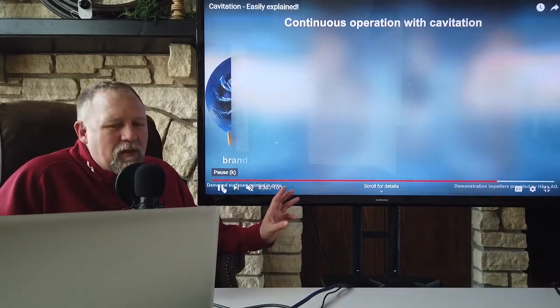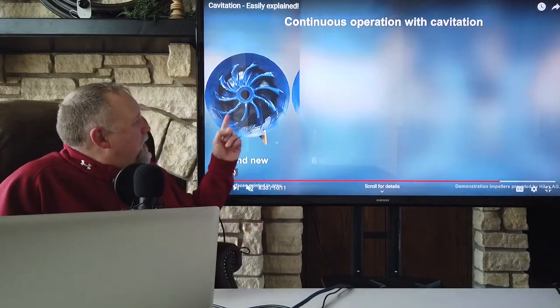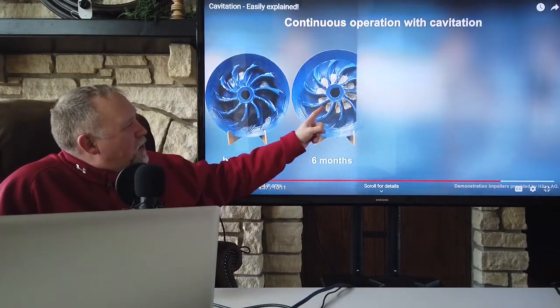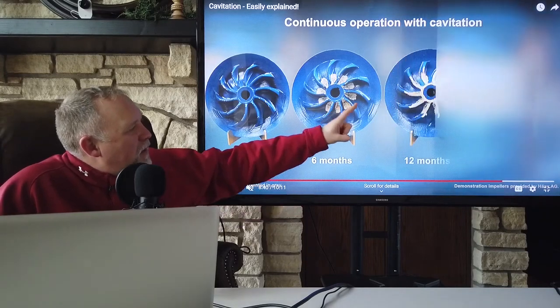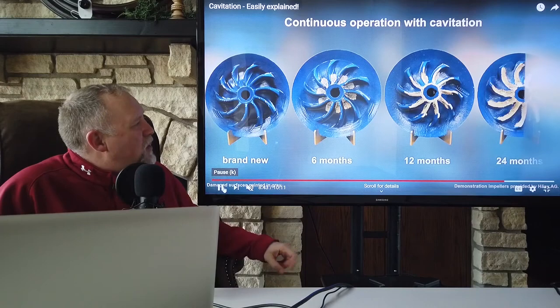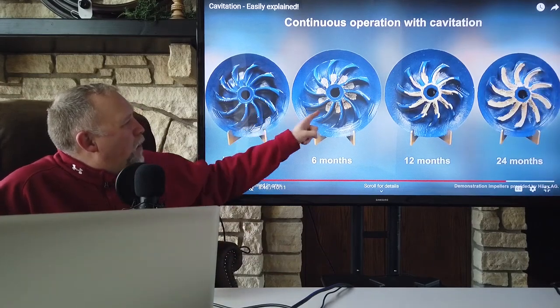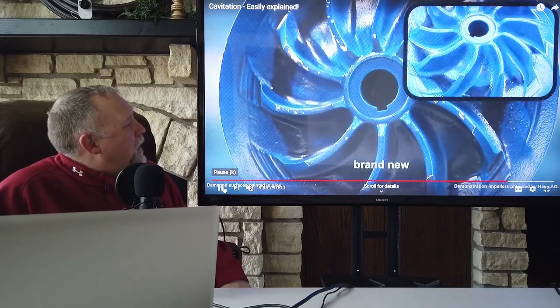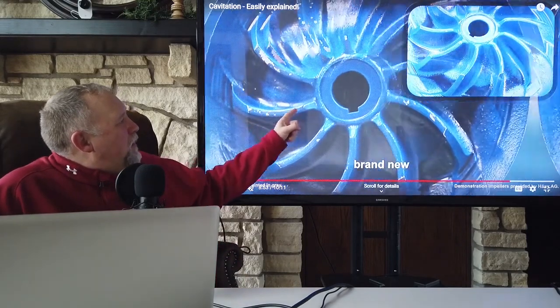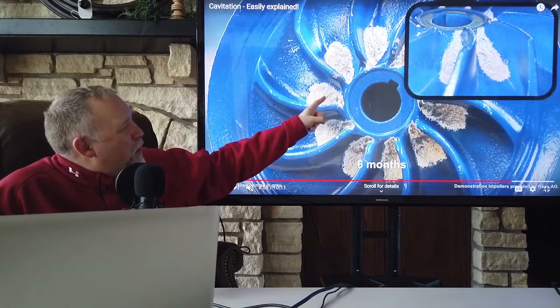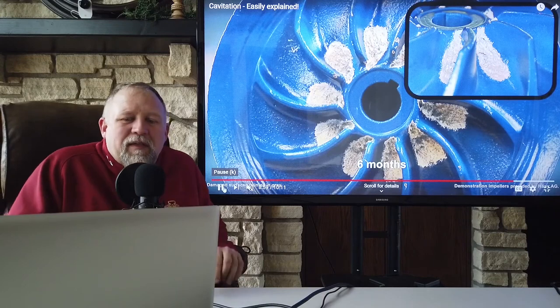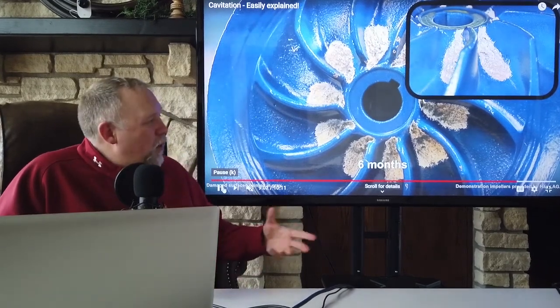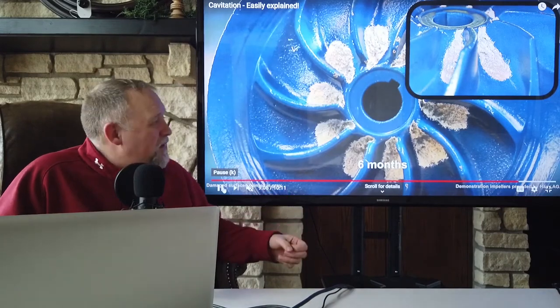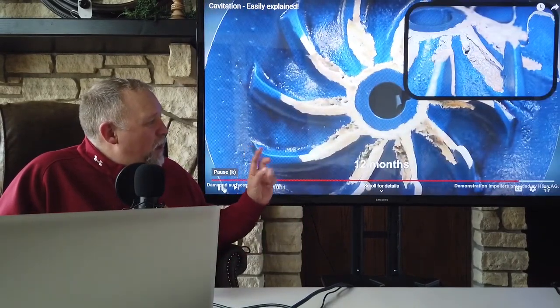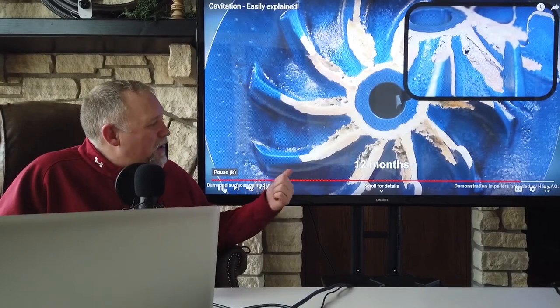And we have an example of a normal impeller, one that wasn't subjected to cavitation, right? This one happens to be brand new. And then these gray areas illustrate after a few months of cavitation, 12 months of cavitation, and then a year of cavitation. What you'll see is the metal wearing away at the edges of these surfaces, all right, start to erode the blue finish off of them and actually rip apart the impeller itself. This can happen on any impeller material, whether it be brass or steel, even stainless steel. This will happen. And then over time, as that happens again and again and again, it can erode it.